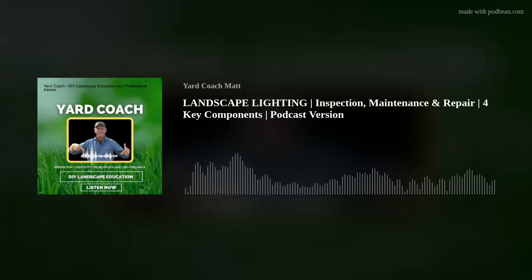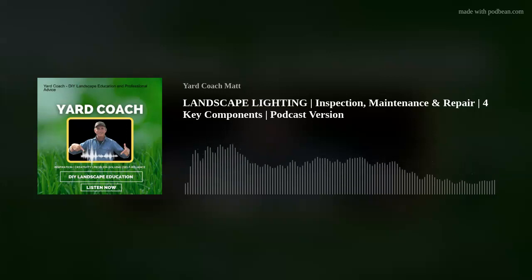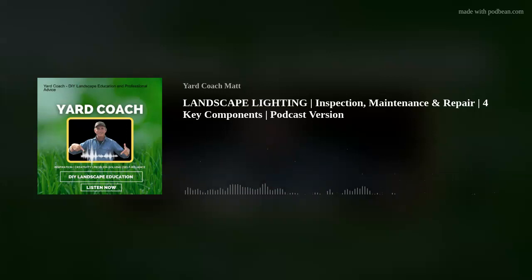Ninety percent of the time, in my experience, it was always the bulb. Especially the older incandescent bulbs, which are really going out of style, and I'll address that in a minute. If the fixture is subjected to a lot of sprinkler water all the time, the bulb seats, where the bulb actually gets plugged in, and the connections throughout the whole fixture can really get deteriorated and rust out.